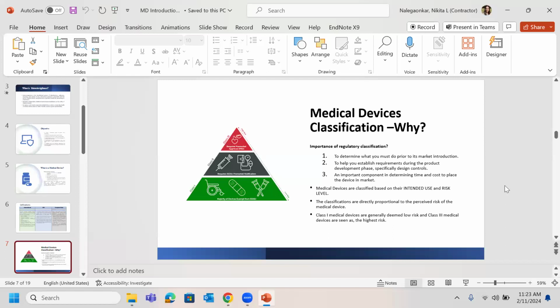So these are the different classifications. For the European region, they are class 1, class 2A, class 2B, and class 3 devices. These are the levels of risk, and it is totally based on the intended use of the device. What is the purpose of your device? That determines the risk classification. For the FDA there are class I, class II, and class III, and in the Indian market also class A, B, C and D.